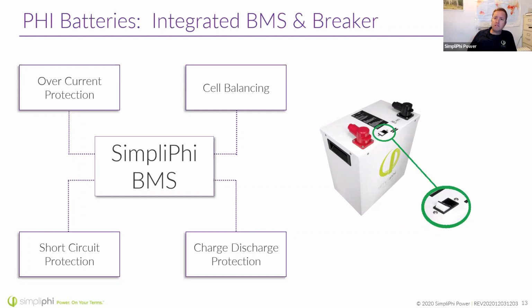Really, a battery management system is doing cell balancing. That's the main reason it's in there. But it can also offer other protections: overcurrent protection, short circuit protection, charge and discharge protection. It's kind of the last line of defense. It's never an excuse for a poorly programmed or poorly sized system, but if it doesn't see things it likes, the battery management system is simply going to open itself up to protect it.